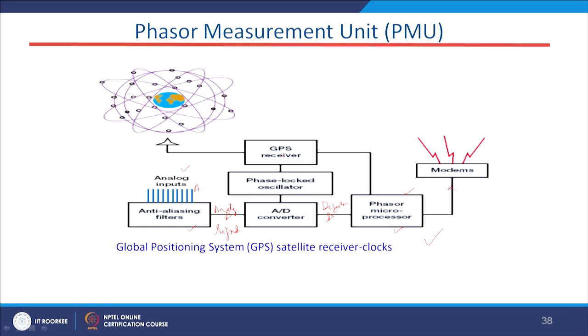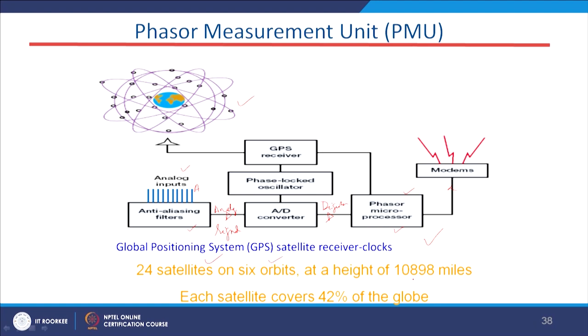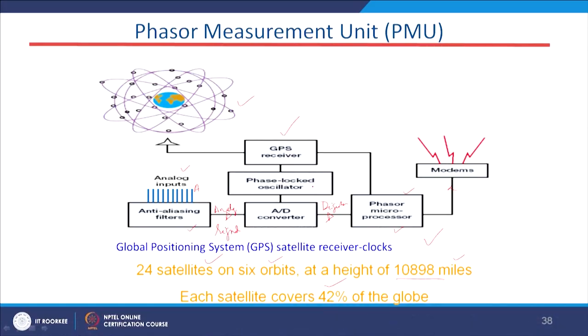The GPS component has 24 satellites on 6 orbits at a height of 10,898 miles; each satellite covers 42% of the globe. The GPS receiver receives satellite signals and supplies them to the phase-locked oscillator, which locks the sampling frequency according to the GPS receiver signal. One pulse per second (1 PPS) is received by the GPS receiver, which triggers the ADC to begin sampling the voltage and current signals.